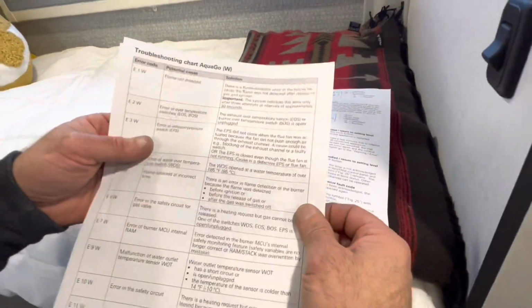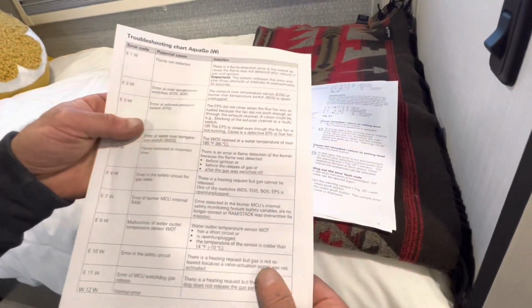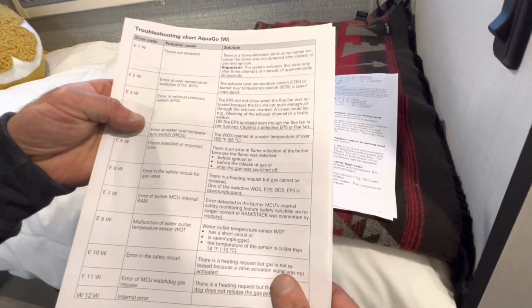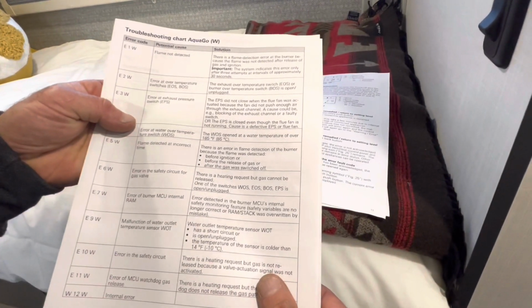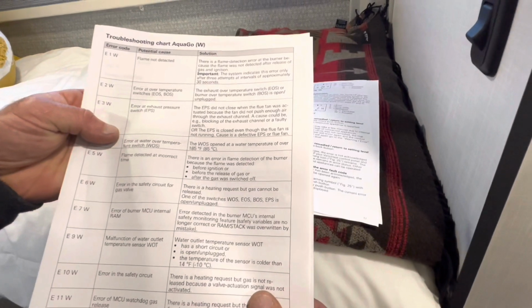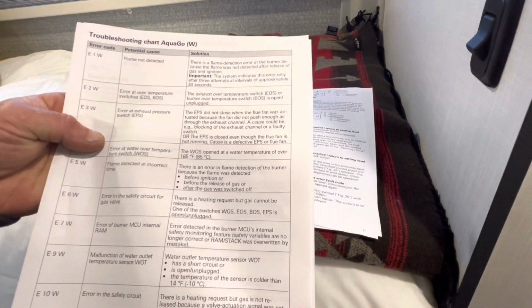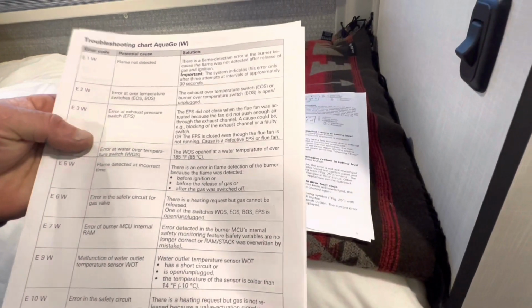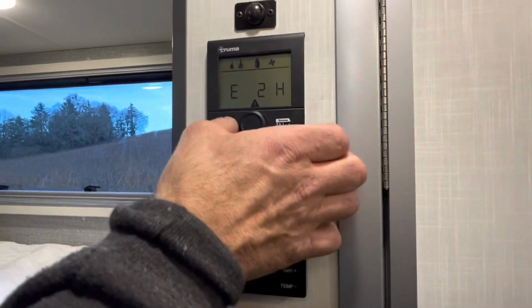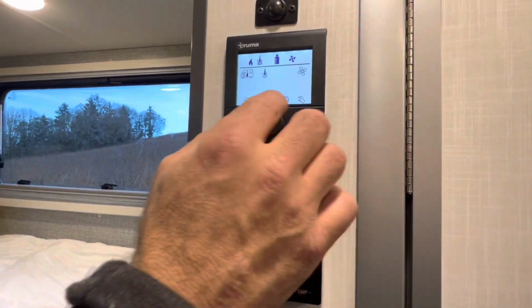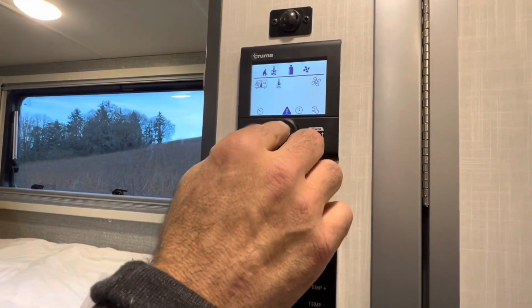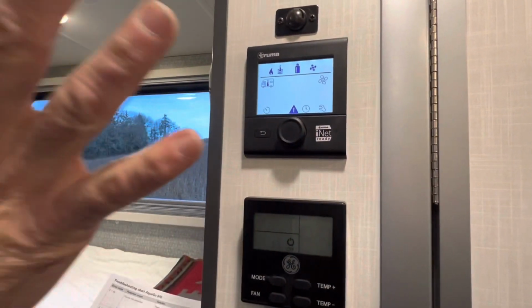So let's go over to the troubleshooting chart, and it says error at over temperature switches: the exhaust over temperature switch, EOS burner over temperature switch BOS is unplugged. Well, there was also an error code that came up with E16, and we're going to make that happen again. Bear with me, oh, something critical.